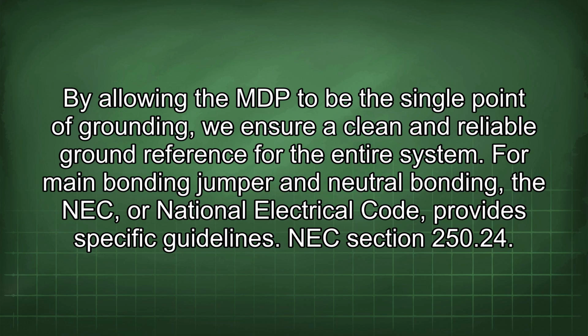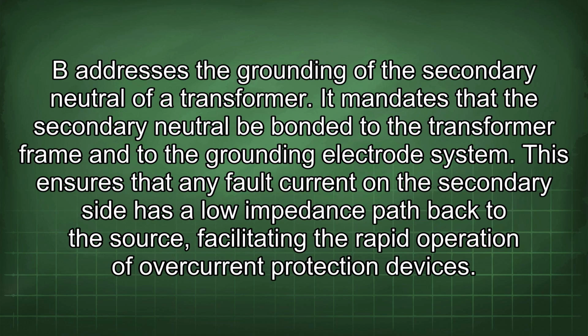NEC Section 250.24(B) addresses the grounding of the secondary neutral of a transformer. It mandates that the secondary neutral be bonded to the transformer frame and to the grounding electrode system. This ensures that any fault current on the secondary side has a low impedance path back to the source, facilitating the rapid operation of overcurrent protection devices.